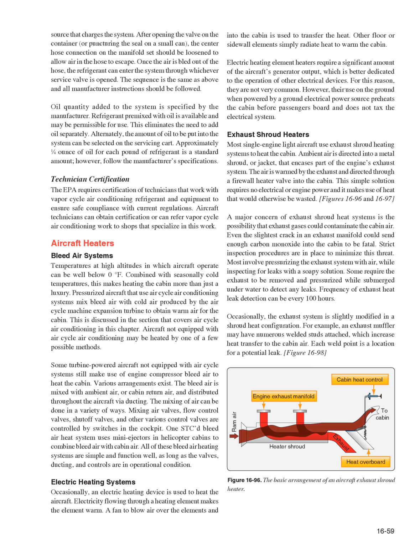Oil quantity added to the system is specified by the manufacturer. Refrigerant premixed with oil is available and may be permissible for use. This eliminates the need to add oil separately. Alternately, the amount of oil to be put into the system can be selected on the servicing cart. Approximately 1/4 ounce of oil for each pound of refrigerant is a standard amount, however, follow the manufacturer's specifications.